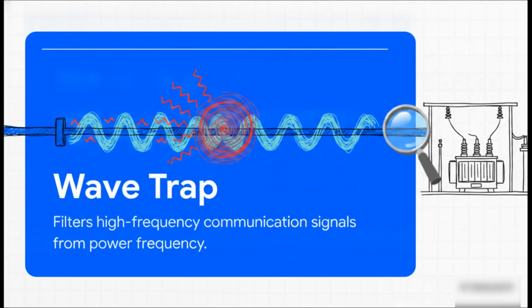Okay, here's a really cool, slightly surprising fact. Those giant power lines do a lot more than just carry electricity. They actually carry high-frequency communication signals, which allow different substations to talk to each other almost instantly. To manage this, a device called a wave trap acts as a filter. It ensures those high-frequency communication signals don't flow into the local substation equipment and get lost, all while allowing the standard low-frequency 50 or 60 hertz power to pass through completely uninterrupted.